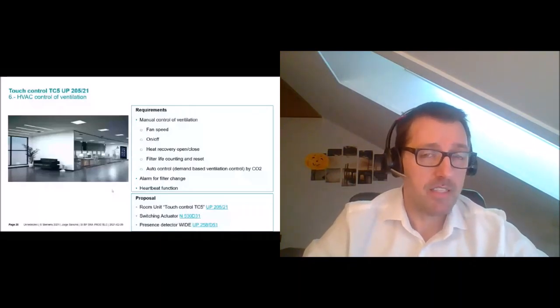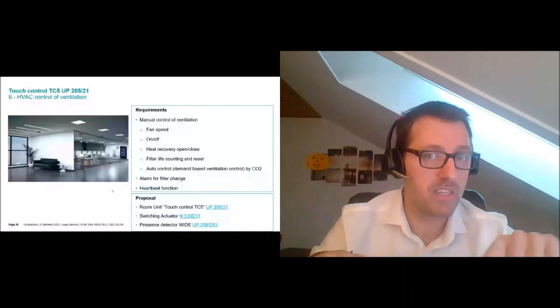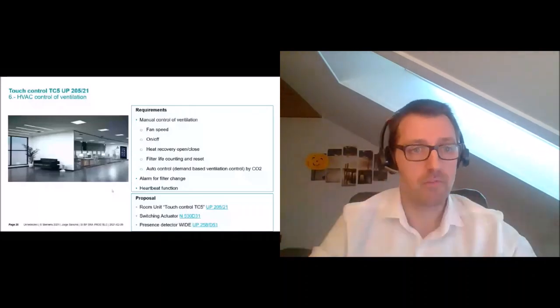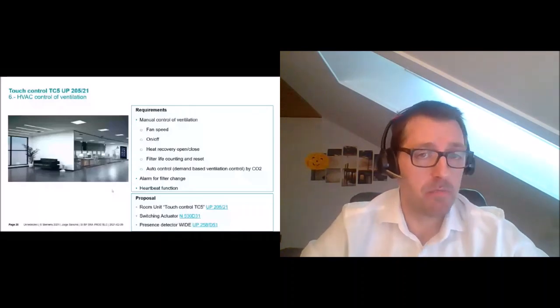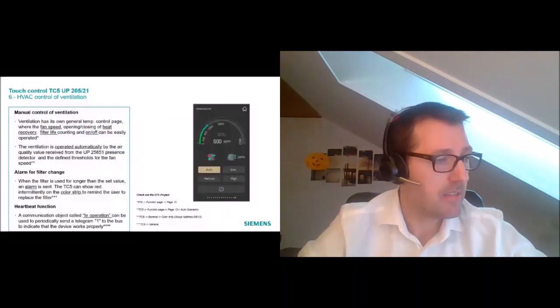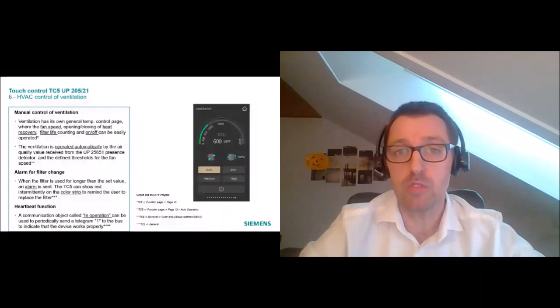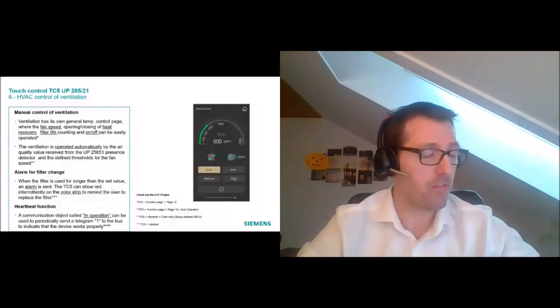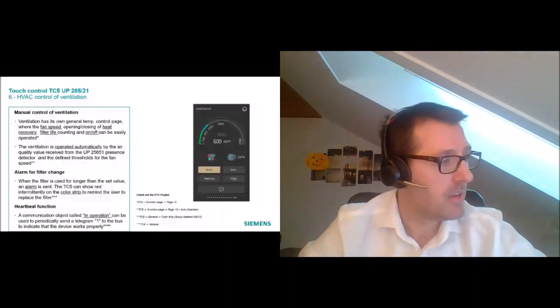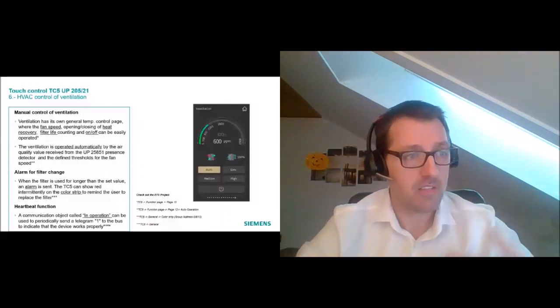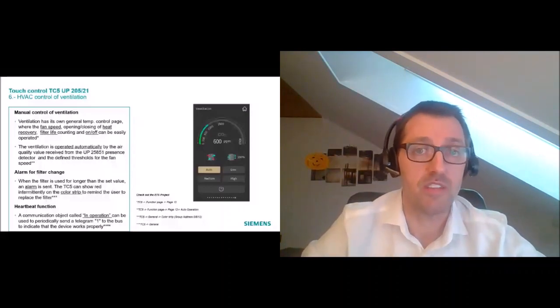The TC5 has a built-in temperature sensor, but we need to receive the CO2 value from the bus. In this case we can use the presence detector Wide, which has built-in temperature, humidity, and CO2 sensors — or any other KNX sensor. This CO2 value is the reference the TC5 uses to control the ventilation.